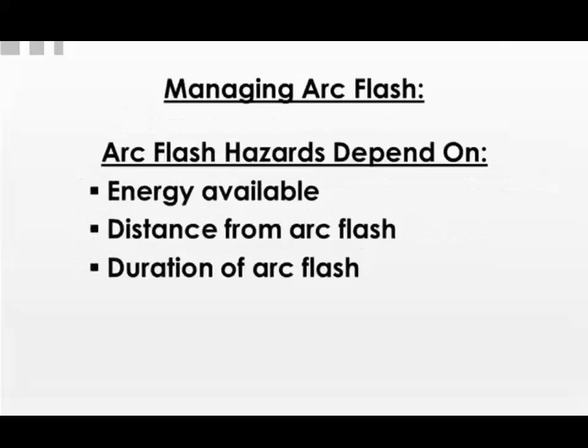Okay, so we talked about in arc flash what the hazards are. Let's talk about managing arc flash. So arc flash hazards depend on the energy available, the distance from the arc flash, and the duration of the arc flash. So the more distance you can put between an employee that's authorized and the piece of equipment, the better.